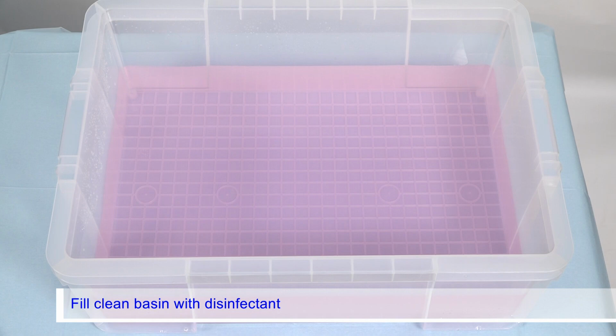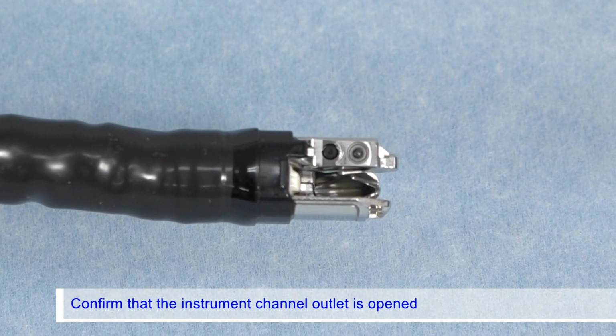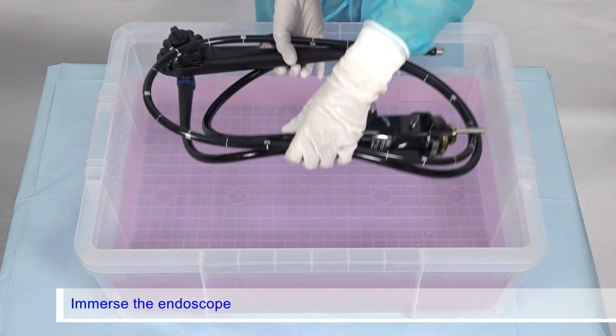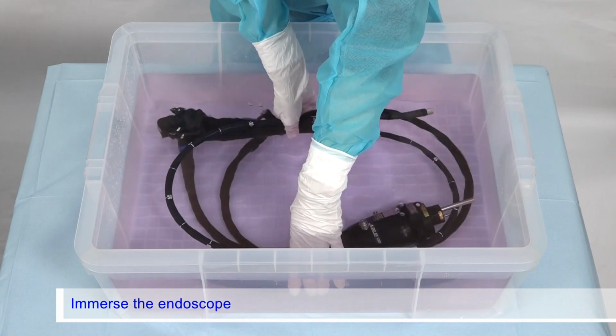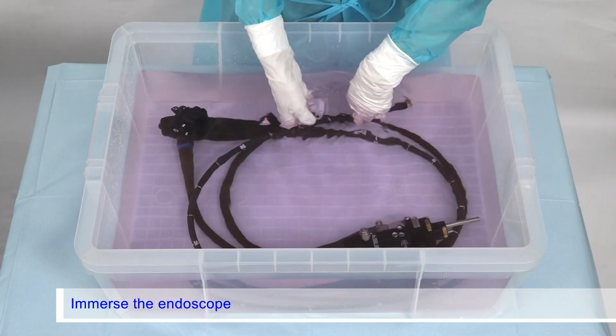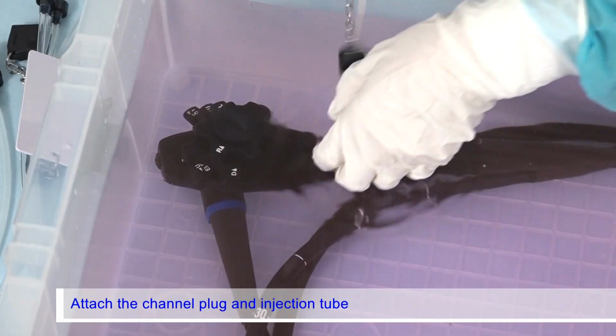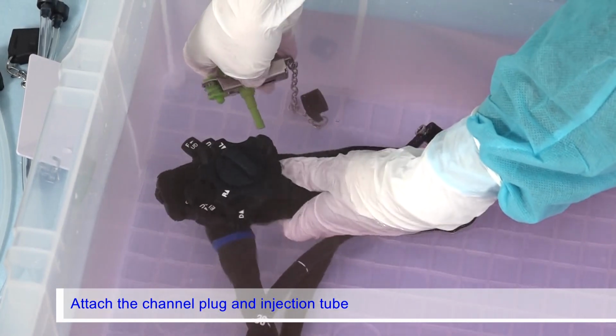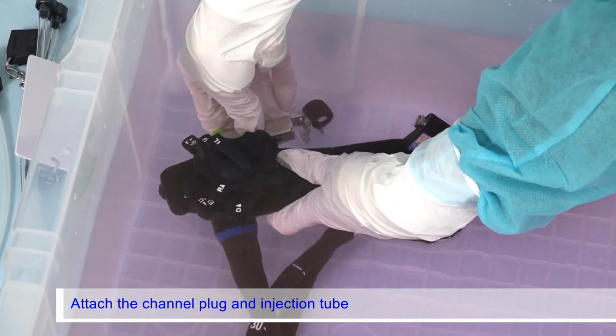Fill a clean, large basin with the disinfectant solution according to the manufacturer's instruction manual. Confirm that the instrument channel outlet of the distal end is opened. Completely immerse the endoscope in the disinfectant solution. Attach the channel plug and the injection tube to the endoscope.